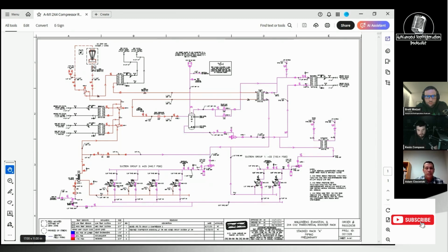Now, one of the challenges we have had and designed around on this rack is in the wintertime, how do we have enough heat? Because the design of this store required a lot of heat in the wintertime. And we know that during the wintertime, a lot of refrigeration load goes away. It may be running 25%, if not lower at part times. So it's very difficult then to get full design THR out of a rack if you don't have the refrigeration side then to produce a THR.